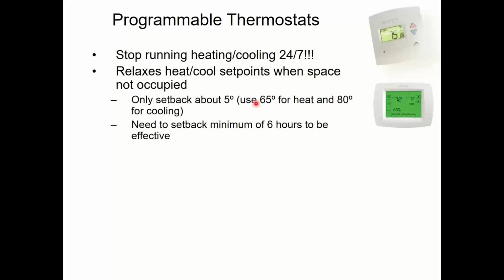It'll depend on your building and how fast it can recover the next morning. But 5 degrees is a pretty good starting point for trying it out. On the cooling side, if you have a 75-degree set point, let it relax up to 80 degrees at night as an initial step, an initial trial run. You might be able to go a little bit more. And then you need about 6 hours for this to start being effective.